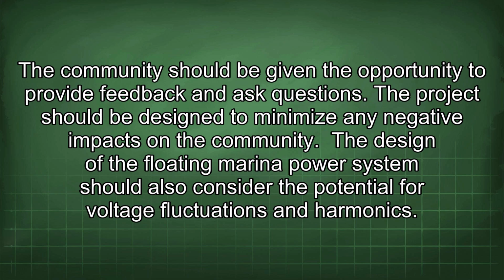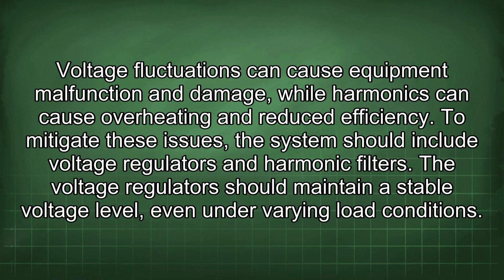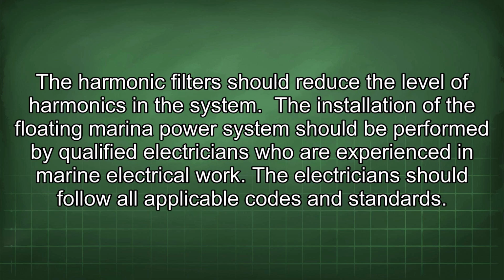The design of the floating marina power system should also consider the potential for voltage fluctuations and harmonics. Voltage fluctuations can cause equipment malfunction and damage, while harmonics can cause overheating and reduced efficiency. To mitigate these issues, the system should include voltage regulators and harmonic filters. The voltage regulators should maintain a stable voltage level, even under varying load conditions. The harmonic filter should reduce the level of harmonics in the system.